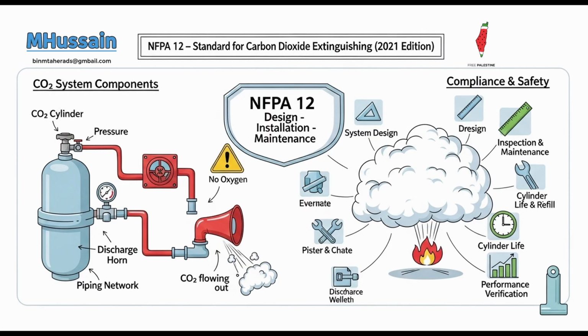Now, for deep-seated fires, which involve solid combustibles like paper, wood, or textiles, the requirements change significantly. Things that smolder inside. Exactly. These fires smolder deeply, requiring the extinguishing concentration to be maintained for an extended period, typically a minimum of 20 minutes. 20 minutes minimum the whole time. Because the CO2 needs to penetrate deep into the material to cool and smother those hidden embers. The quantity here is based on fairly tight enclosures, and specifically accounts for thermal insulating effects, using specific flooding factors. Need more gas for longer, basically.